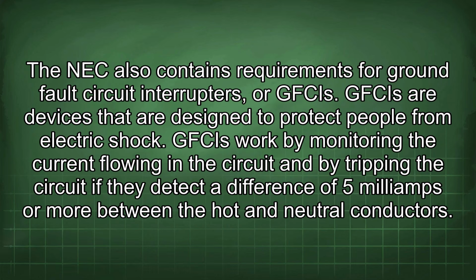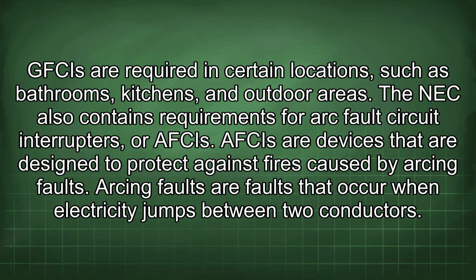The NEC also contains requirements for ground fault circuit interrupters, or GFCIs. GFCIs are devices that are designed to protect people from electric shock. GFCIs work by monitoring the current flowing in the circuit and by tripping the circuit if they detect a difference of 5 mA or more between the hot and neutral conductors. GFCIs are required in certain locations such as bathrooms, kitchens, and outdoor areas.